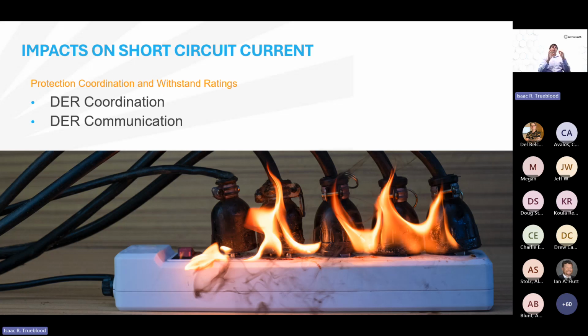A major difference between a transmission interconnected generating site and a distributed energy resource is that the system strength for a distribution system is much weaker, as we kind of talked about in our previous slide. This makes the difference between a load current and a fault current much lower. Transmission faults can be 10 times the load current. So you can have a load of 100 amps, and when it faults, it's 1,000 amps. Distribution system faults, especially near the end of feeders, can be as low as 2 times the load current. If you have 100 amps, it could be a 200 amp fault. The room for protection coordination and preventing these unnecessary power losses is a much tighter fit for these distribution systems.